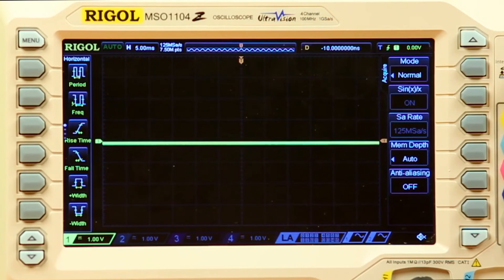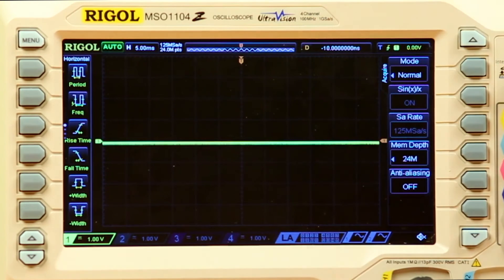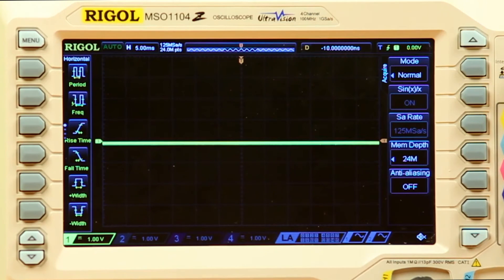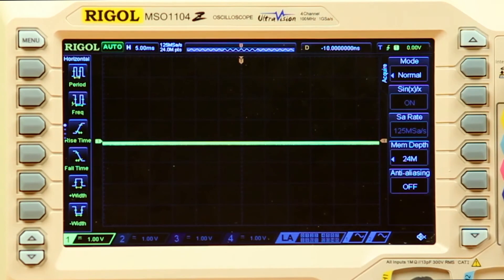Now when we set the memory depth to an independent number, to a given value, it uses the maximum sample rate possible that still fills that display. Often this configuration leaves much of the waveform off the display, as we can see from the gray areas here — data on the left and right of the display.